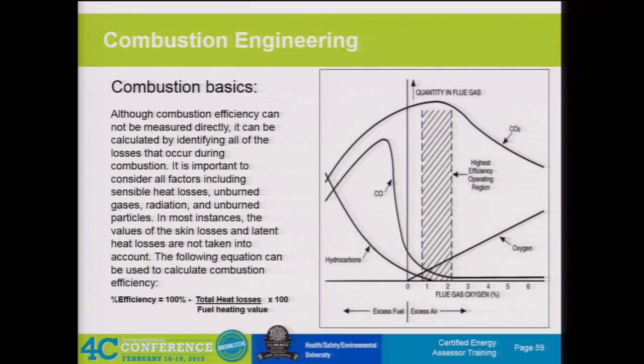So trying to find the sweet spot—we're measuring CO, the oxygen, and hydrocarbons and looking at tuning to find that low point. There's a component where you increase NOx as well. As the rule kind of speaks to this—they understand that as you drive CO down, at some point you're driving NOx up. And so as you have NOx limits on your units, that has to be maintained. When we do the tune-up, it's not at the expense of NOx. We may actually not get down to this sweet spot if there are permit limits requiring the NOx to be at a certain level—we may have to operate a little bit less efficiently on the CO component in order to meet our NOx limits.